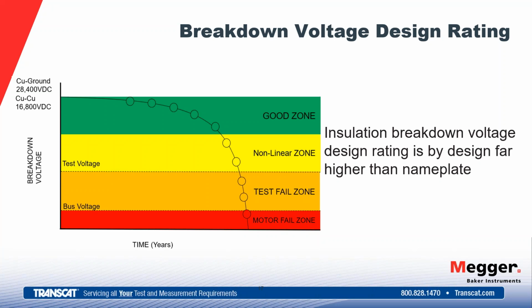Okay, so what we're speaking of is the type of insulation that's being put into the motor. Is it of the nature of thermoplastic, or is it a thermosetting type of insulation? There's no good way of determining that as far as writing; looking at nameplate information, it doesn't tell us that.